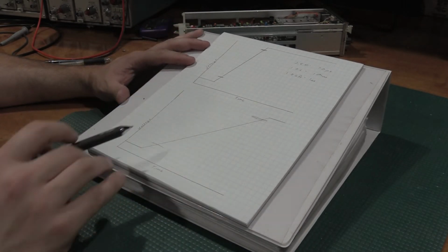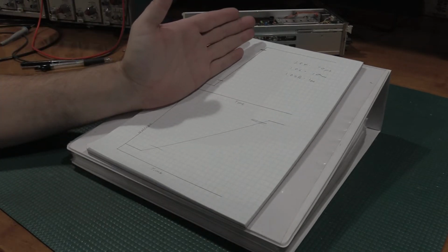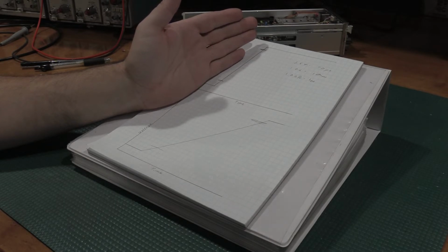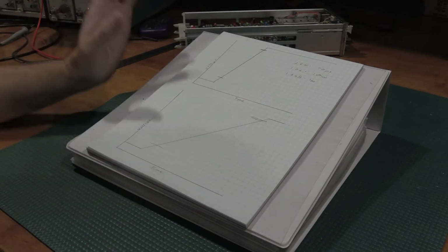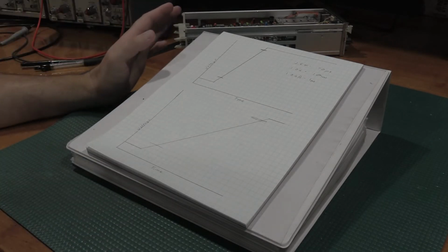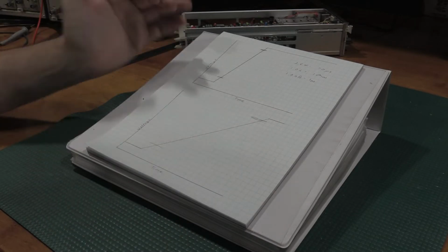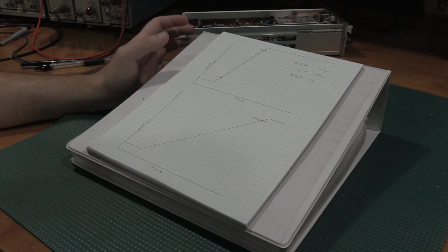Where will this cause someone to struggle during a scope alignment? If you're using a square wave that's too slow, you can't do the high frequency side of the plug-in alignment or scope alignment for a 400 series. My personal recommendation would be, if it looks good, don't adjust the HF compensation. It's very easy to get that out of alignment, and it's hard to get that back into alignment. And if that's out, the measured bandwidth of the scope channel will be affected.